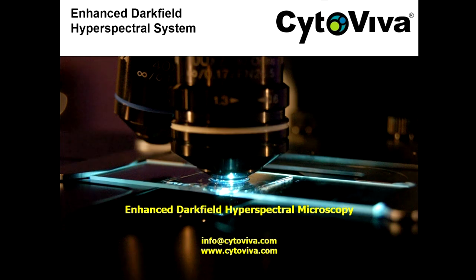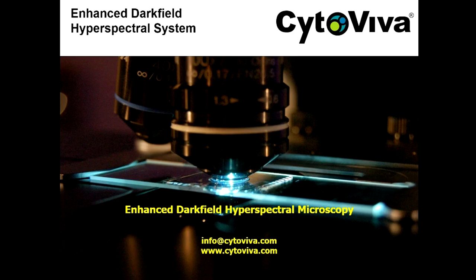Q: Can you combine the software with conventional microscopy? Absolutely — the system typically comes with a dual port so you can have both an optical camera and the hyperspectral camera on the dual-port camera mount. You can capture video, still color images, and hyperspectral images. You can do standard bright field, fluorescence, reflected and transmitted microscopy, as well as optical hyperspectral imaging.